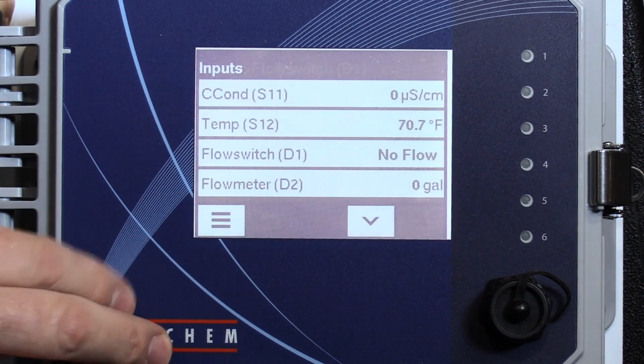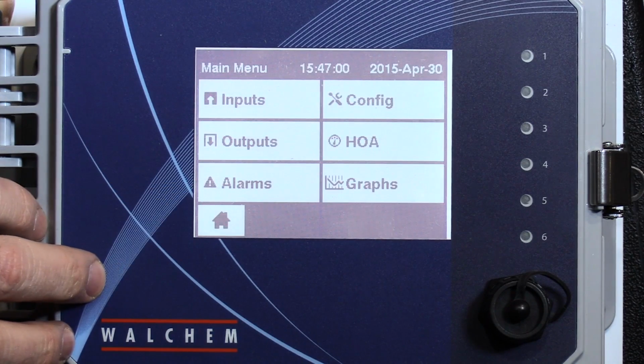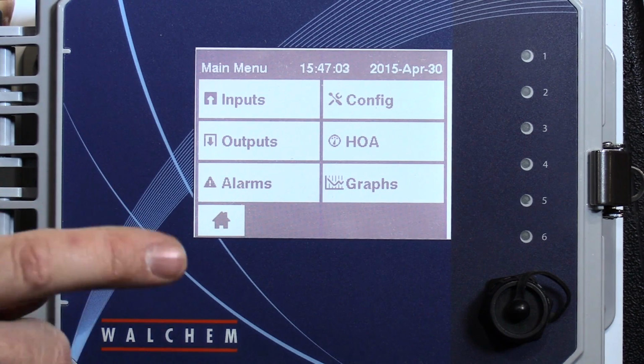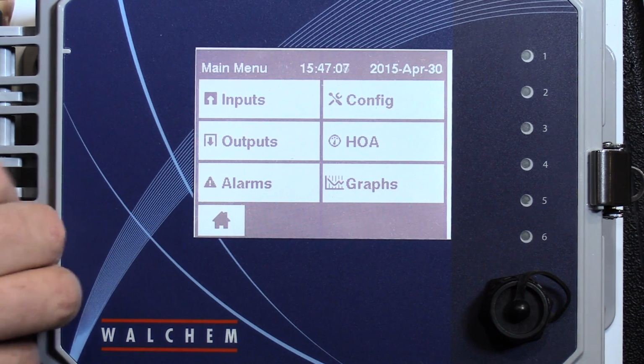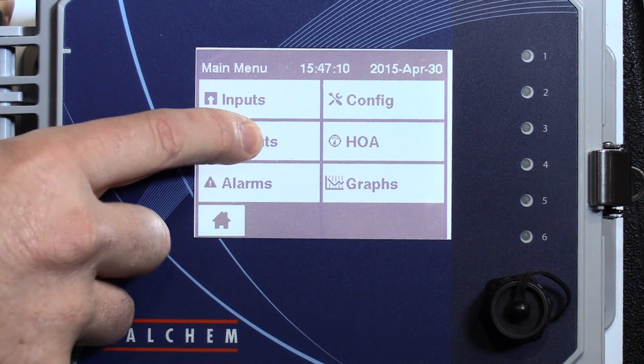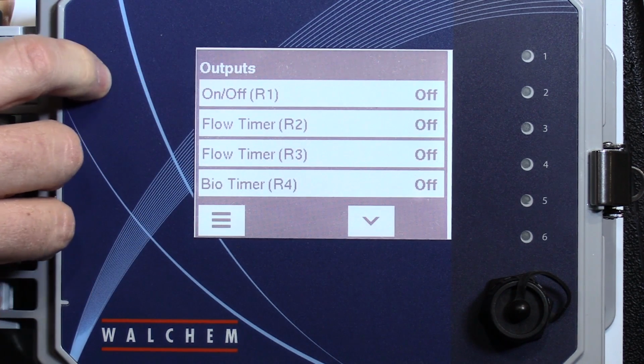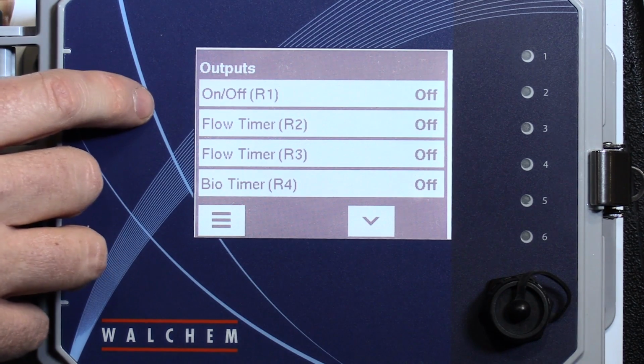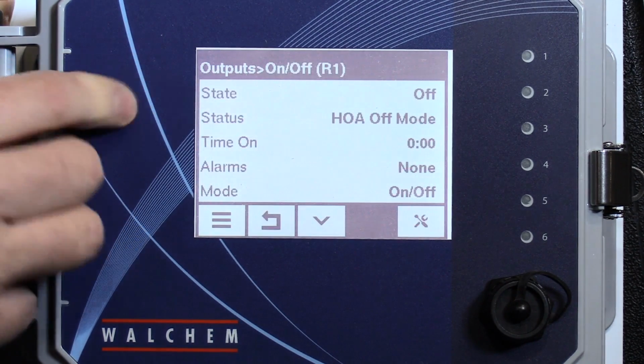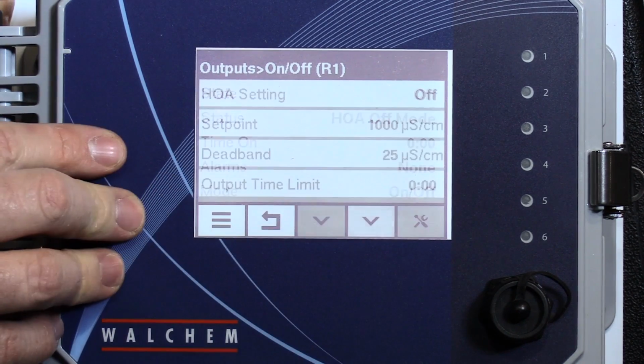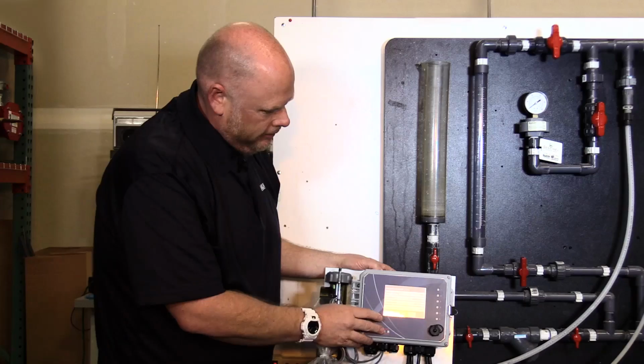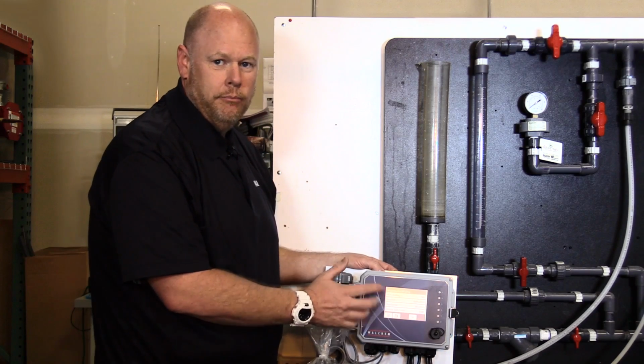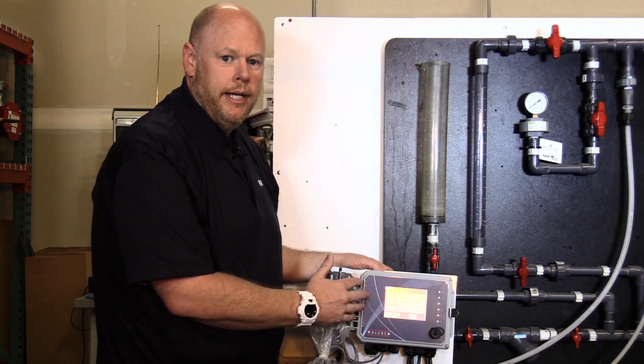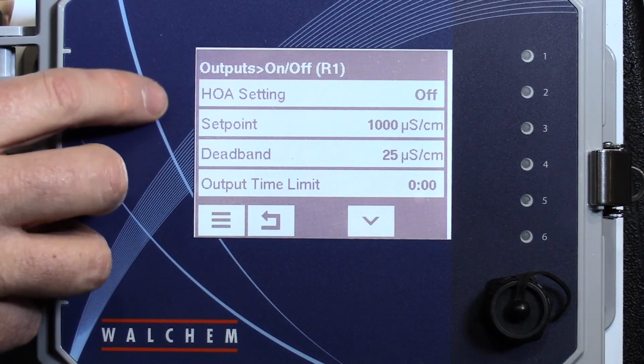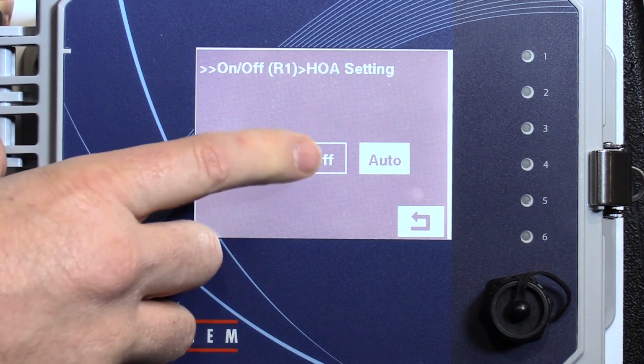Now you would go back to the home button and you want to program the relays to turn on your chemical metering pumps and your solenoid valves. So you would go to outputs. You select which relay you want to control what pump or valve. Relay 1, you decide which way the relay is going to be controlled, whether it's on, off, proportional, time-based. You set the settings to hand, off or auto. Set it to auto.